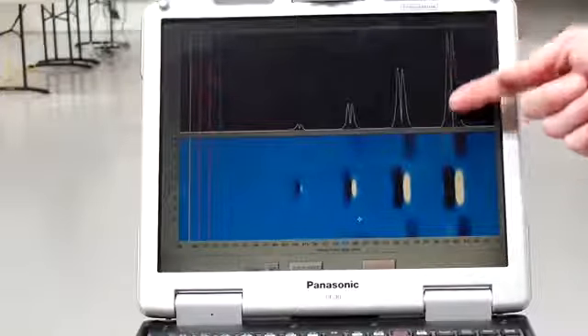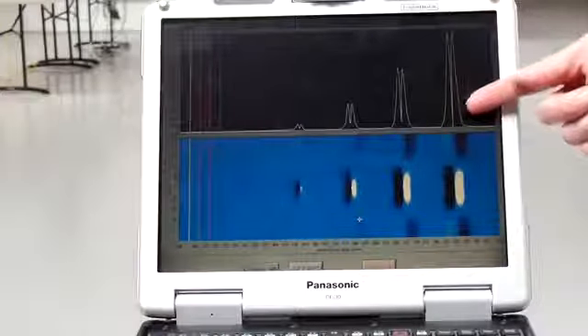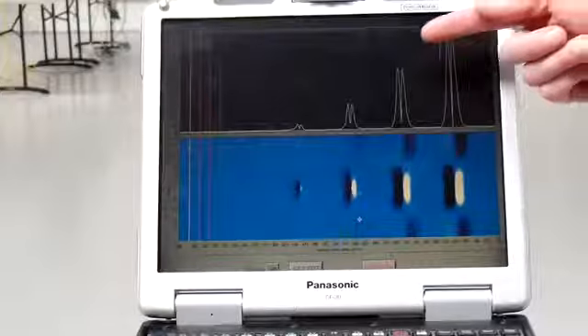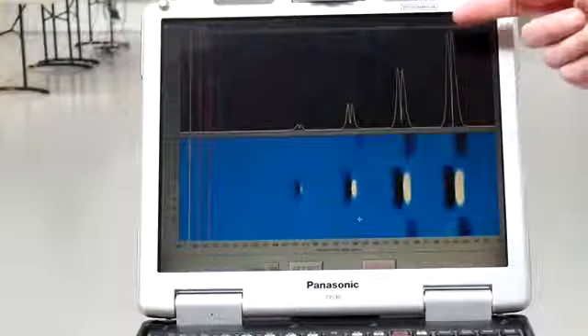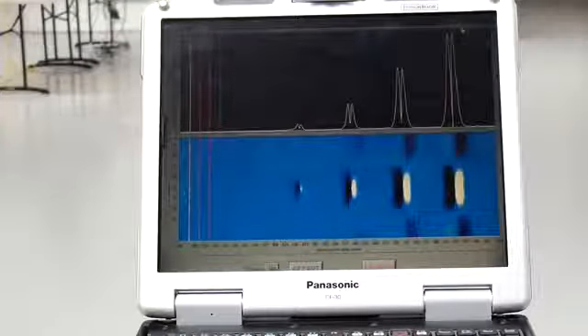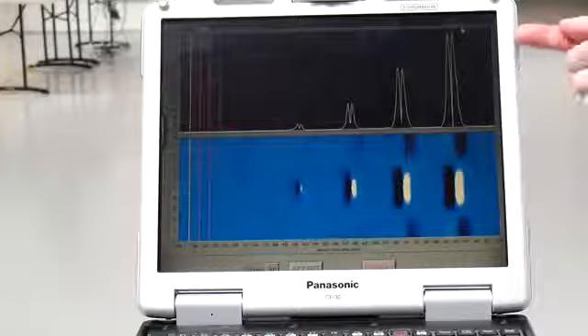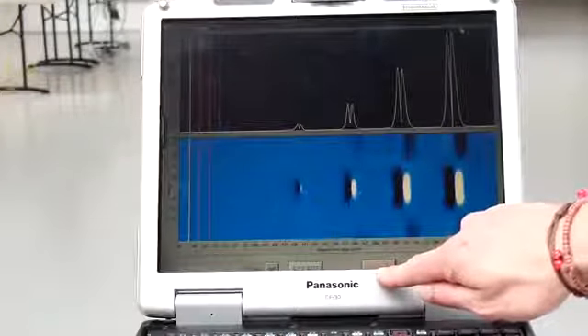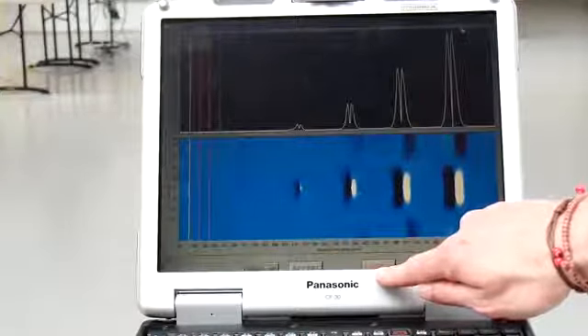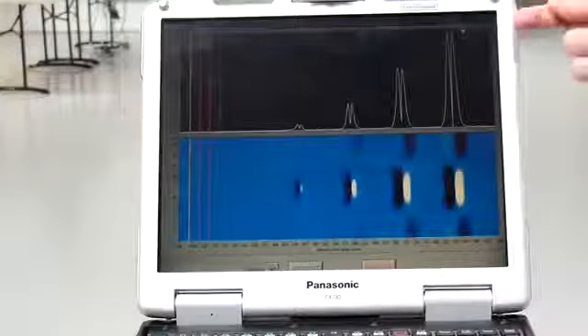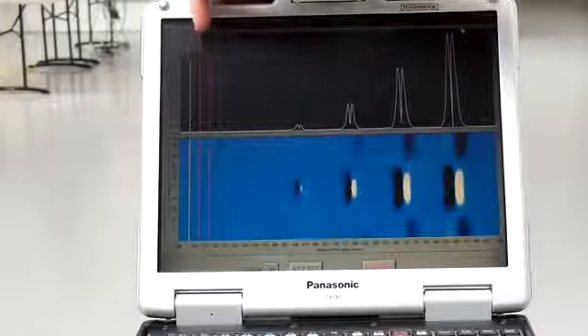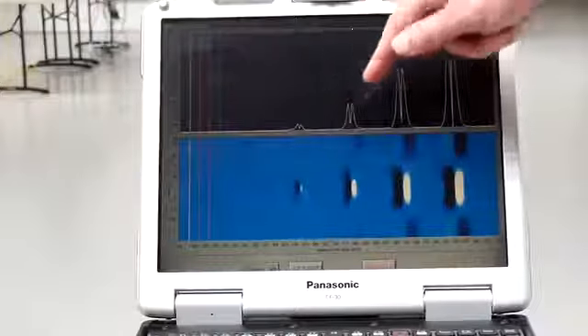The corresponding rectified A scan of each indication is presented on the top pane, and you can check the amplitudes of those are correct. If you're not happy with the calibration, you can click cancel to go back and do it again. If you are happy, the next step will be to position the gates over the echoes. I've completed the first 3 already.